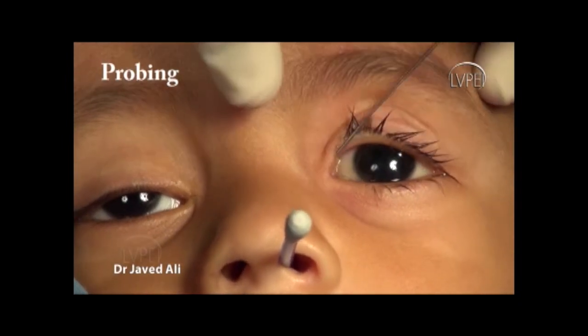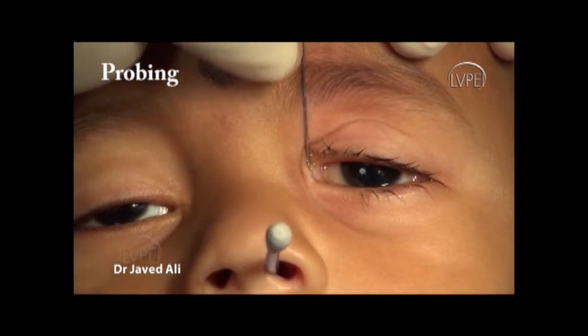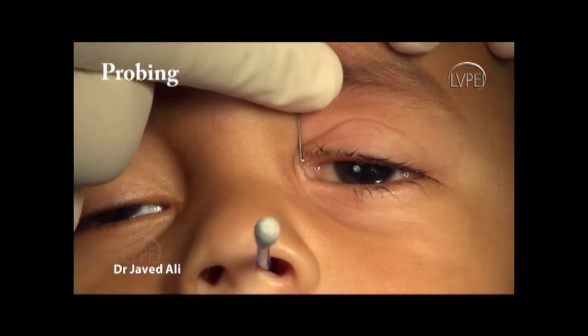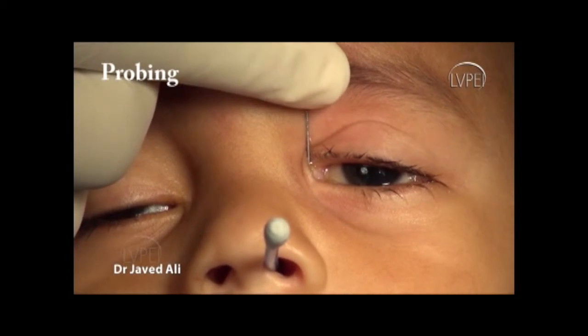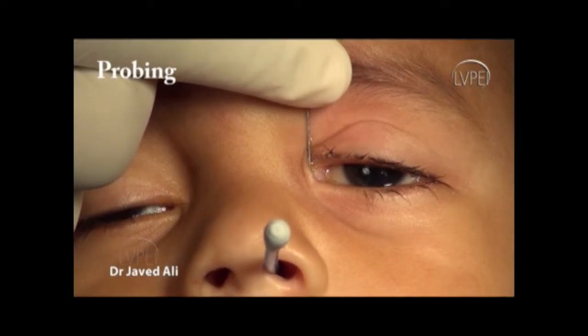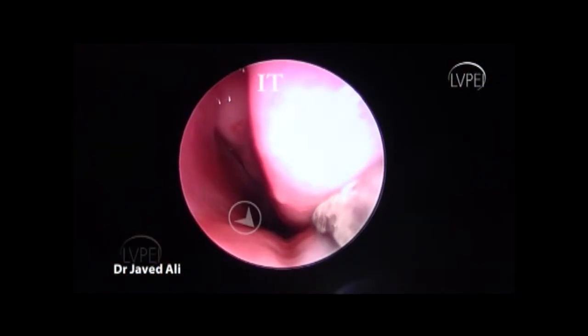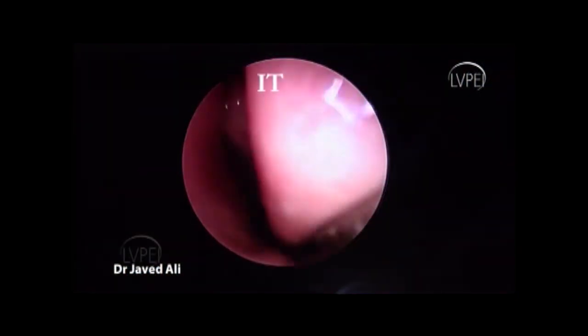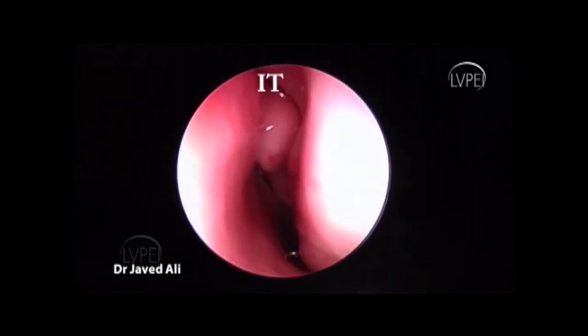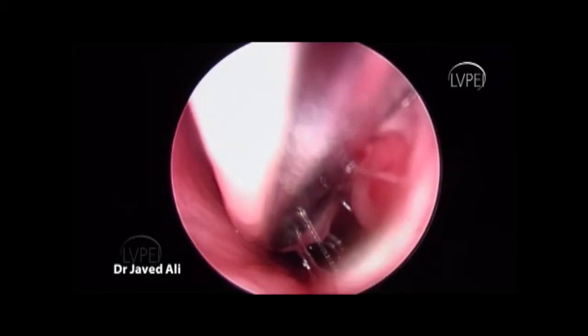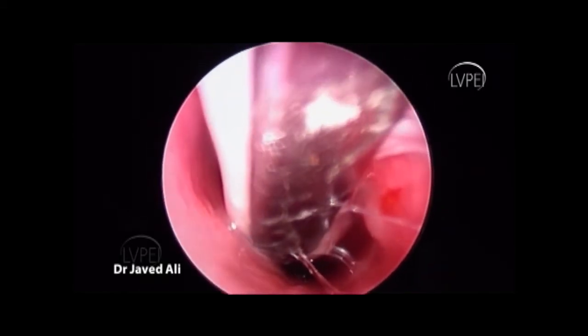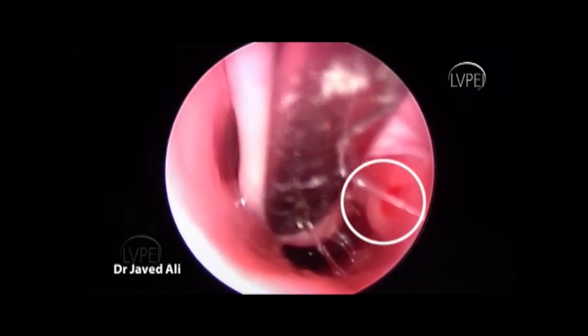lid. Once a hard stop is felt, the probe is then withdrawn by 1 mm and then gently turned 90 degrees to lie flat on the forehead in line with the trochlea. Probe is stabilized using a finger on the superior orbital rim. It is then gently advanced into the lacrimal sac and the nasolacrimal duct in downward, backward, and lateral direction. No undue movements or force should be applied to avoid any false passage. Membranous obstruction at the lower end of the nasolacrimal duct can be overcome with a give way of resistance without application of much force. Probe should be pushed just for a few millimeters further so as to avoid injury to the floor of the nose and subsequently the palate.